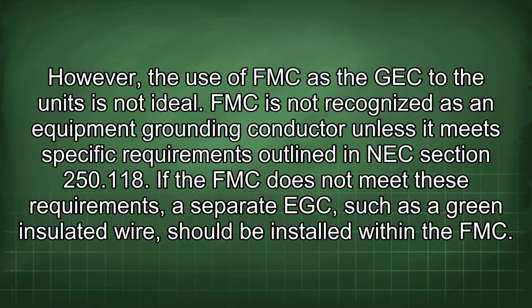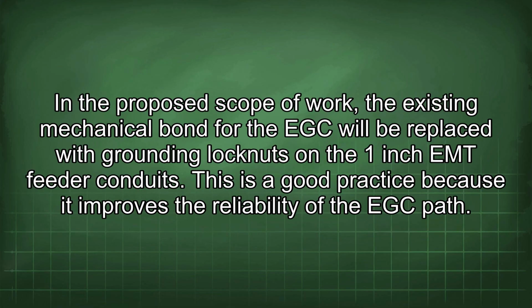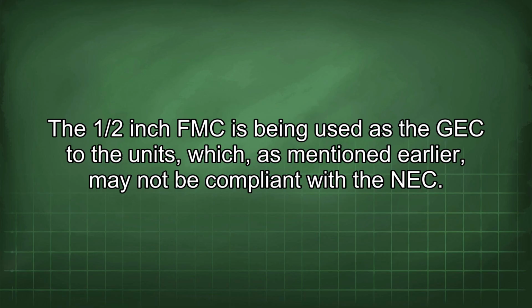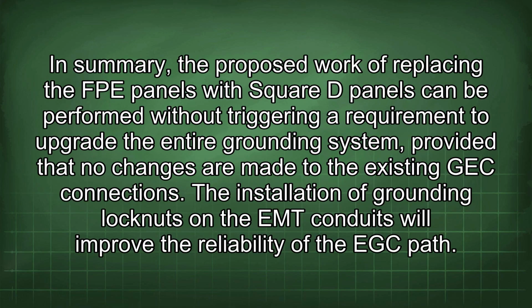installed within the FMC. In the proposed scope of work, the existing mechanical bond for the EGC will be replaced with grounding lock nuts on the 1-inch EMT feeder conduits. This is a good practice because it improves the reliability of the EGC path. The 1/2-inch FMC is being used as the EGC to the units, which, as mentioned earlier, may not be compliant with the NEC.